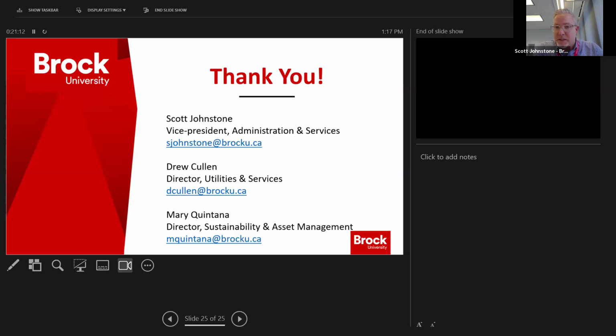For example, in our bioscience building, we have a small life safety generator to satisfy code, but then we have a big backup generator to satisfy systems with a long ramp up time. The code requires bringing online in 10 seconds for life safety on a small unit, but our large unit for the bioscience building, for example, has a 90-second ramp up time and 120-second phase transfer. So there's a whole bunch of complications.